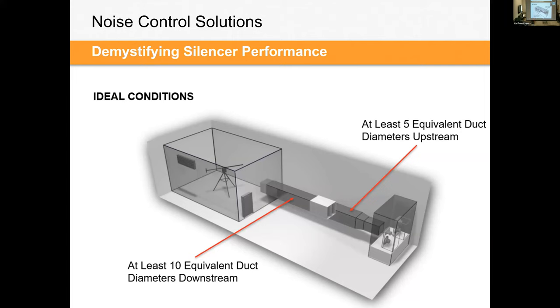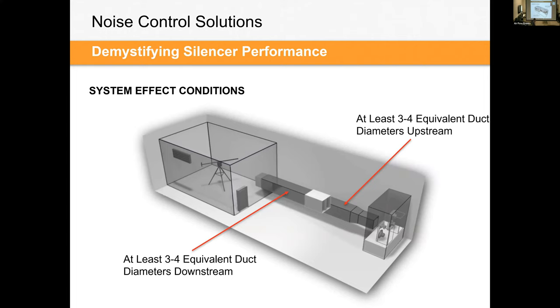Going back to our lab that we learned about earlier, something you should know is that we test under ideal conditions, and you can see it in that silencer flow test here, that there's a long straight run of duct and that silencer goes in the middle where there's 5 equivalent duct diameters upstream and 10 equivalent duct diameters downstream, a very long 60 feet of duct, which never happens in practical installation. Space is tight in every building and you never have the perfect area to install a silencer. In general, we typically try and allow 3 to 4 duct diameters up and downstream, but even that is often a stretch. Sometimes you're close coupled, you have a junction or a fan or a takeoff directly adjacent to it.